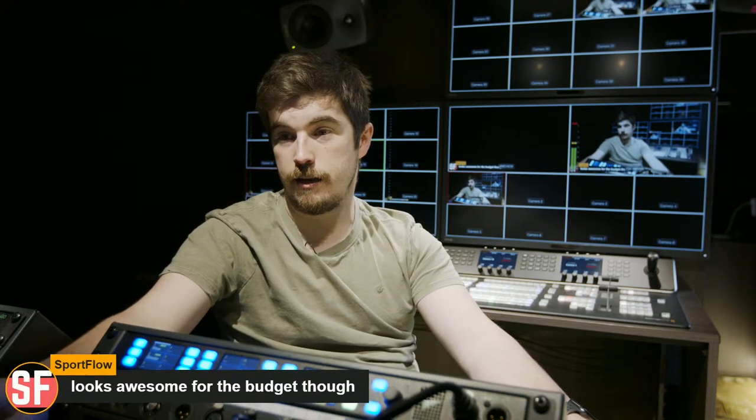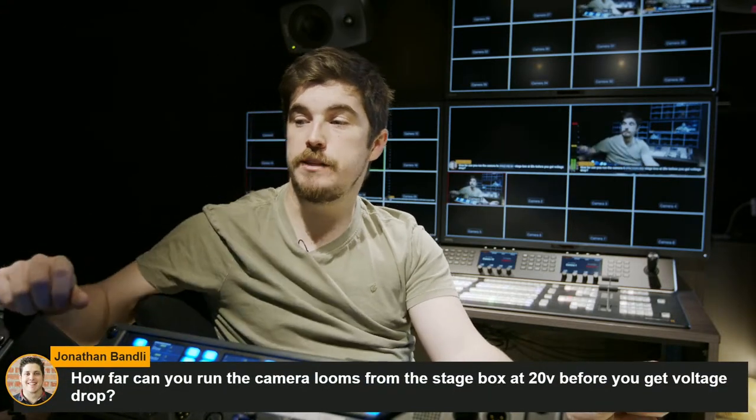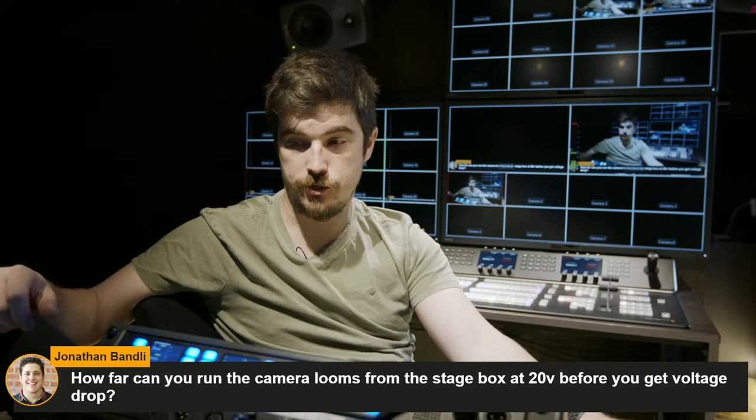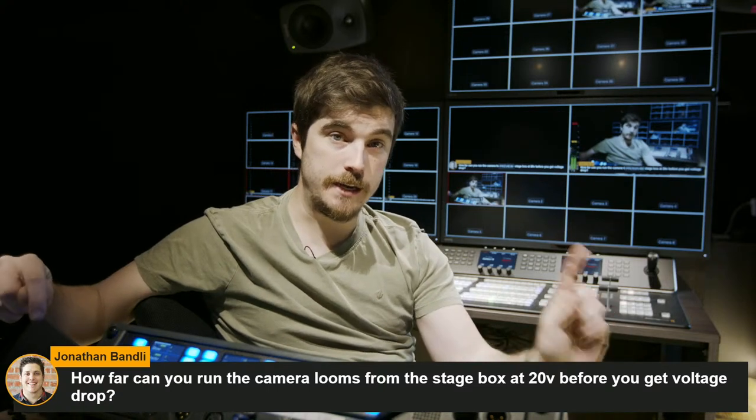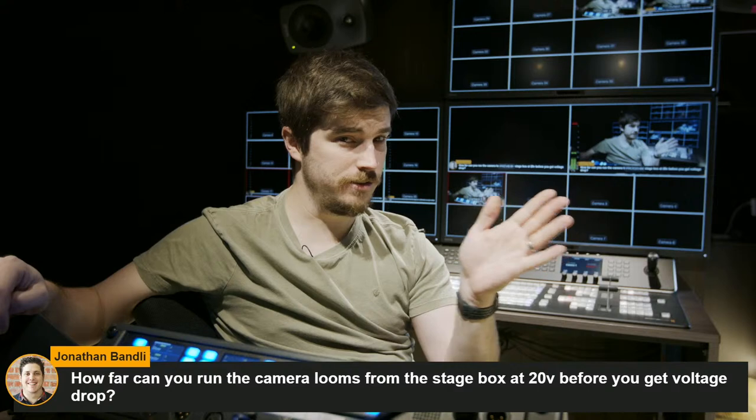Thank you. I think so as well. Now, good question, Jonathan. How far can you run the camera looms from the stage box at 20 volts before you get voltage drop? I picked 20 volts because that is the max voltage for the cameras. It goes between 8 and 20, I think. Obviously, over DC, long distance, you are going to get a voltage drop.